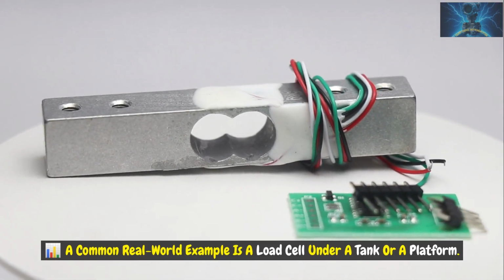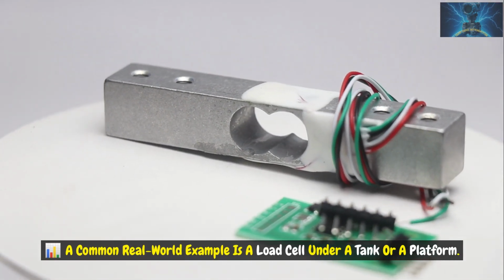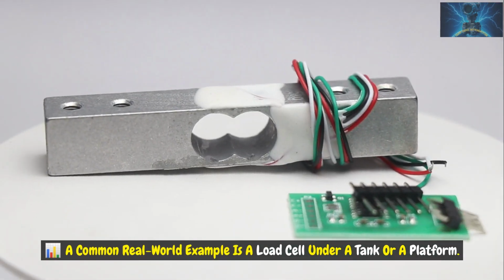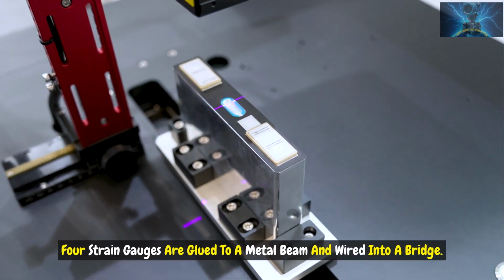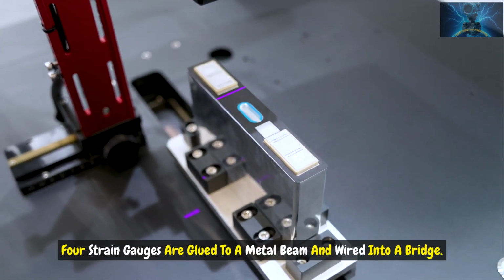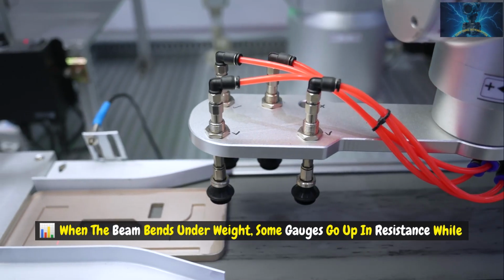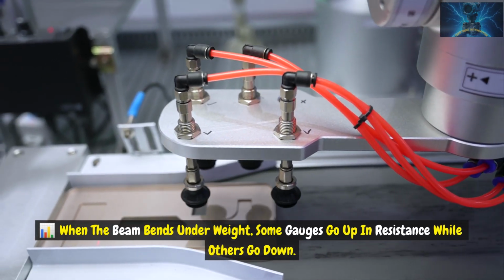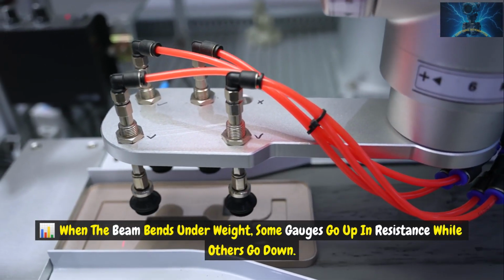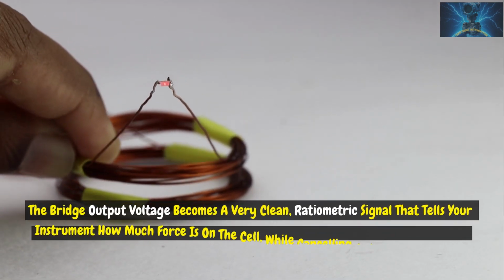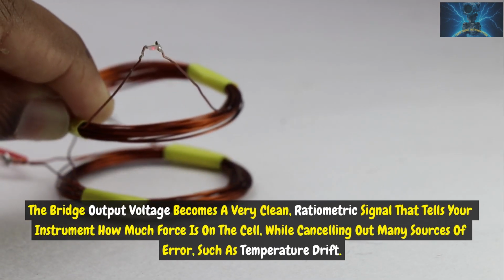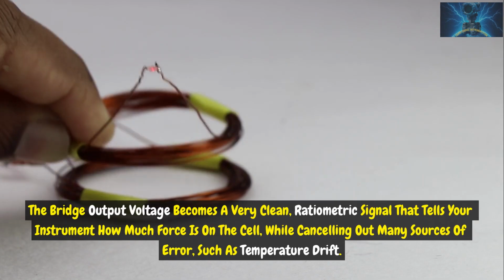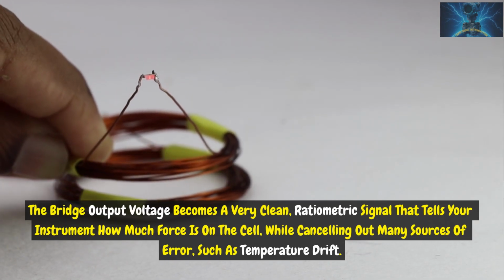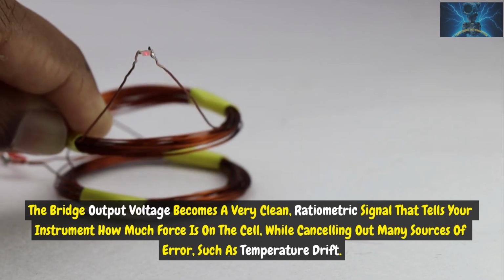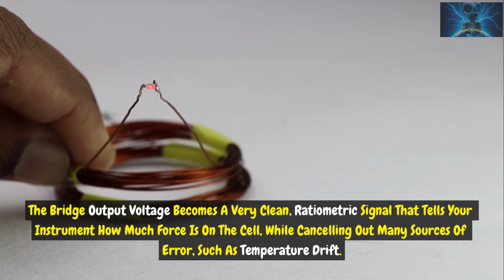A common real-world example is a load cell under a tank or a platform. 4 strain gauges are glued to a metal beam and wired into a bridge. When the beam bends under weight, some gauges go up in resistance while others go down. The bridge output voltage becomes a very clean, ratiometric signal that tells your instrument how much force is on the cell, while canceling out many sources of error, such as temperature drift.